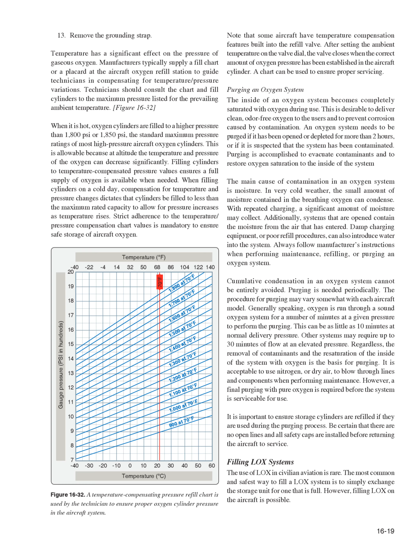The main cause of contamination in an oxygen system is moisture. In very cold weather, the small amount of moisture contained in the breathing oxygen can condense. With repeated charging, a significant amount of moisture may collect. Additionally, systems that are open contain the moisture from the air that has entered. Damp charging equipment, or poor refill procedures, can also introduce water into the system. Always follow manufacturer's instructions when performing maintenance, refilling, or purging an oxygen system.